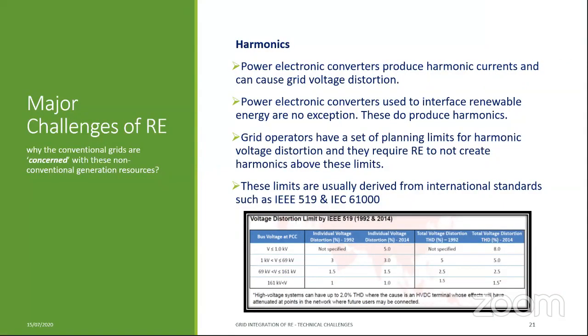Now, when you go to the grid operator and say that I'm going to connect a 100 megawatt wind farm, they will ask you what the harmonic injection into the grid is. If it comes out that this wind farm is causing the THD to go beyond 2.5%, they are eligible to reject the connection until the developer goes back and comes up with a solution to fix that. Requirements are mostly centric around IEEE.